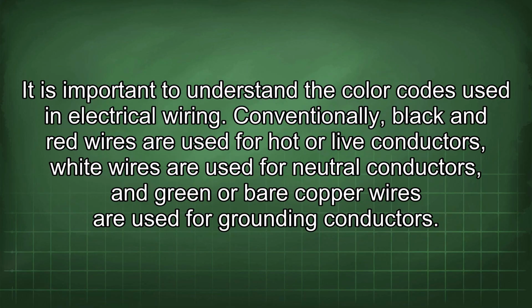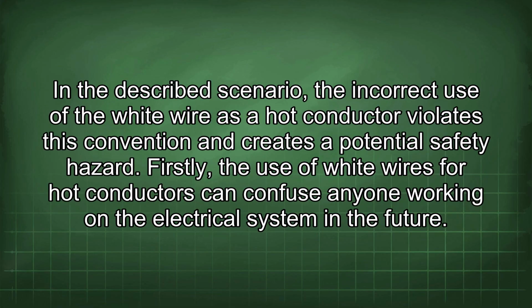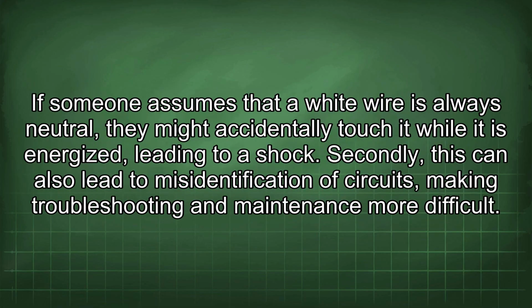It is important to understand the color codes used in electrical wiring. Conventionally, black and red wires are used for hot or live conductors, white wires are used for neutral conductors, and green or bare copper wires are used for grounding conductors. In the described scenario, the incorrect use of the white wire as a hot conductor violates this convention and creates a potential safety hazard. Firstly, the use of white wires for hot conductors can confuse anyone working on the electrical system in the future. If someone assumes that a white wire is always neutral, they might accidentally touch it while it is energized, leading to a shock.